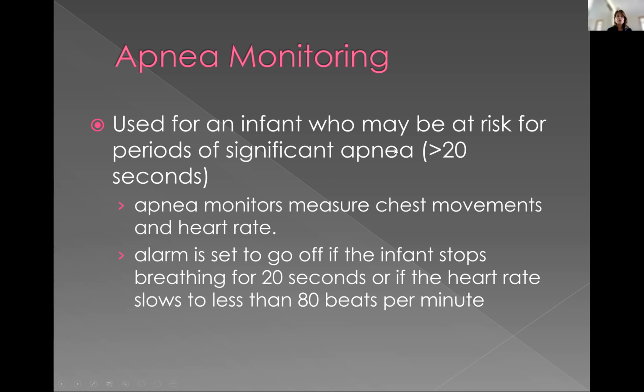How does an apnea monitor work, you ask? Well, let me tell you. So when breathing in and out, the chest expands. And when the chest expands, if there's a belt wrapped around the chest, it's going to notice this change in the thoracic movement, and it registers that as a breath.